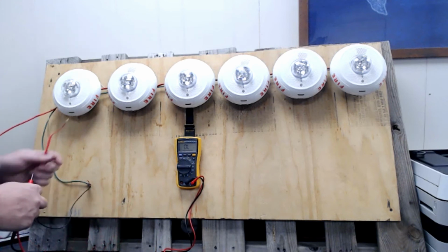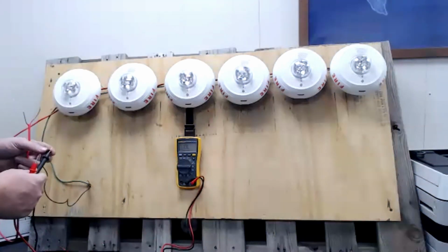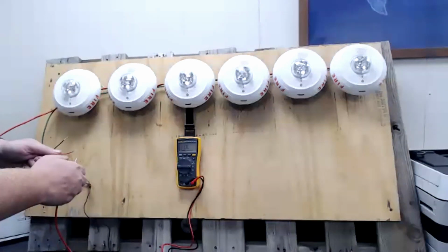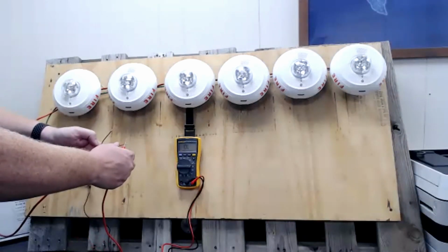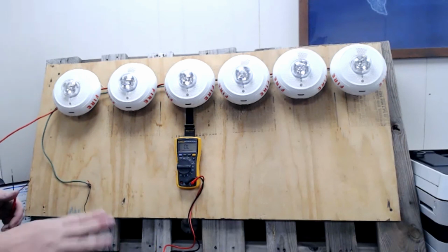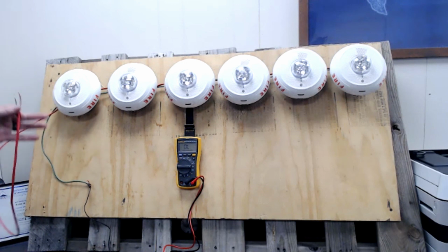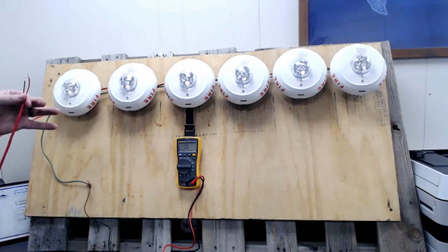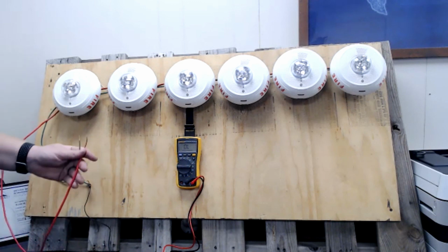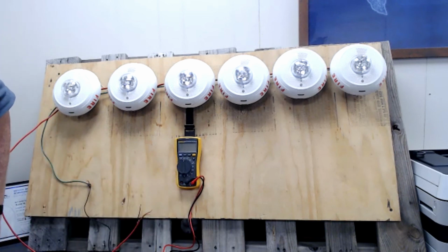So to just finish checking, I showed you we still have our end-of-line resistor, so we didn't cause any other open circuits doing our troubleshooting. I've connected this back to my earth ground little alligator clip. And I check it here, open line at my home run to earth ground on both conductors. Completely open line, no ground reference at all, completely clean wire. We have end-of-line resistance, no reverse polarity devices, no ground reference. This wire is ready to land on a panel. And whenever it lands, it'll come up as a clear circuit, no troubles on it. Look at that, it's right at 12:30.